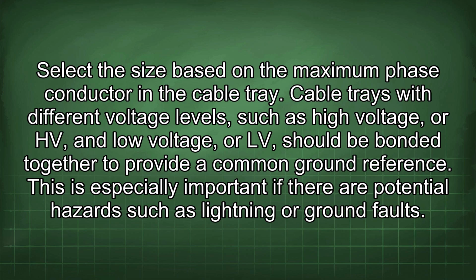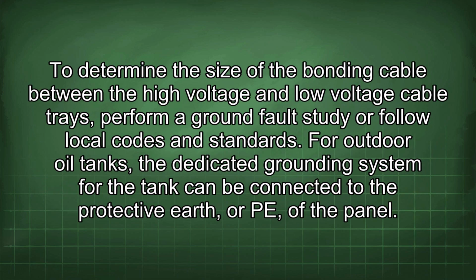Cable trays with different voltage levels, such as high voltage, or HV, and low voltage, or LV, should be bonded together to provide a common ground reference. This is especially important if there are potential hazards such as lightning or ground faults. To determine the size of the bonding cable between the high voltage and low voltage cable trays, perform a ground fault study or follow local codes and standards.